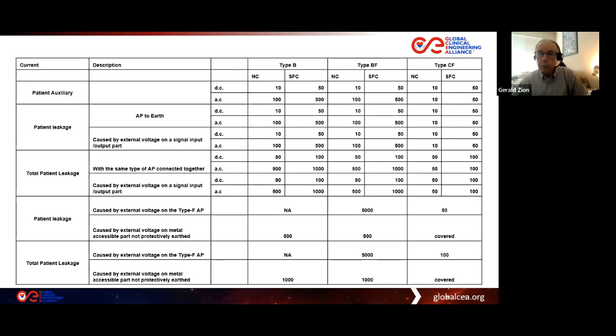I'm not going to go over this one a lot. This one gives you four different medical device patient applied part types. Type B would be a grounded applied part type, patient connection type. BF would be body float, meaning it's isolated, but it is a body isolation. And the most stringent is the type CF or cardiac float, isolated for those kinds of medical devices where the applied part is going to be actually the heart itself or near to the heart itself.